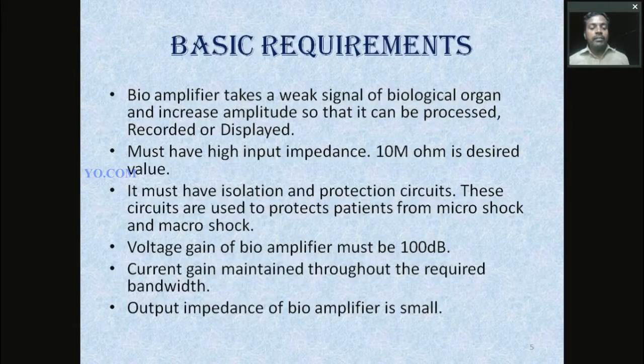The third one is that the voltage gain of the bioamplifier must be 100 dB. dB is decibel, which is a measure of gain. So the voltage gain should be a minimum of 100 dB, because bio signals are very weak, in the range of millivolts or microvolts, and they should be amplified into volts, so we need very high gain.